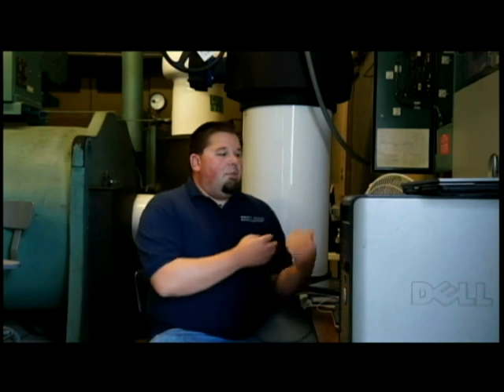So to get back to the sequence that we were going through, a building goes occupied out there, air handler starts up, VAV zones go occupied, and the air handler needs to put out cold air, colder than what is available from outside air. And so it creates a request for chilled water as it opens up its coil valve out there. That in turn passes the flag over here to the central plant where we begin to run our pumps for the chilled water system.